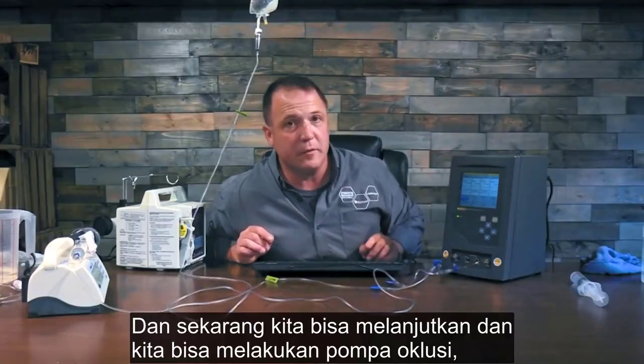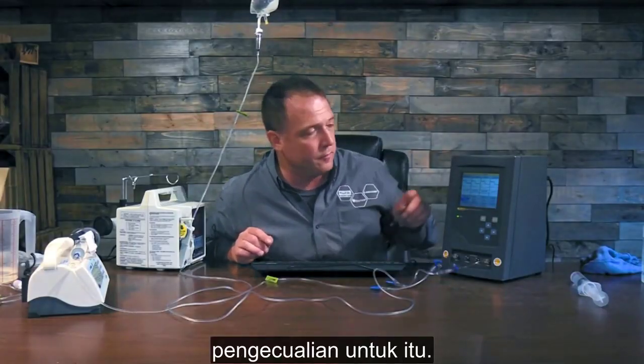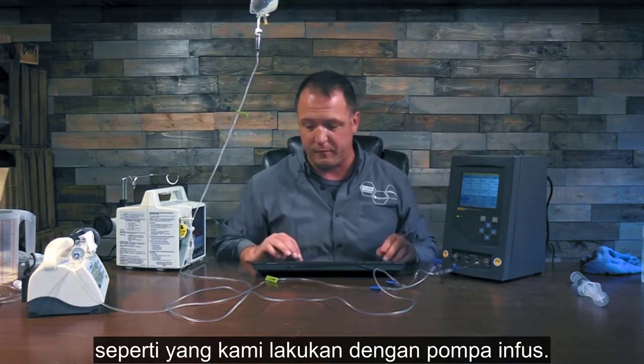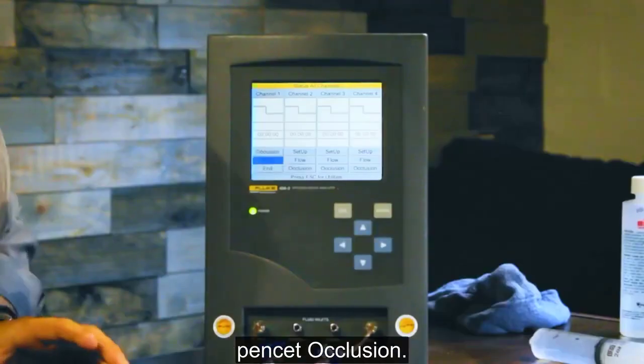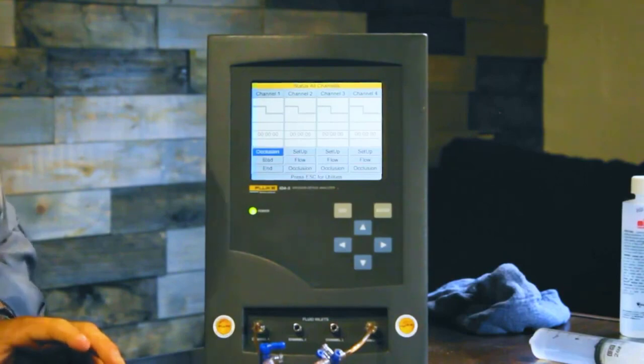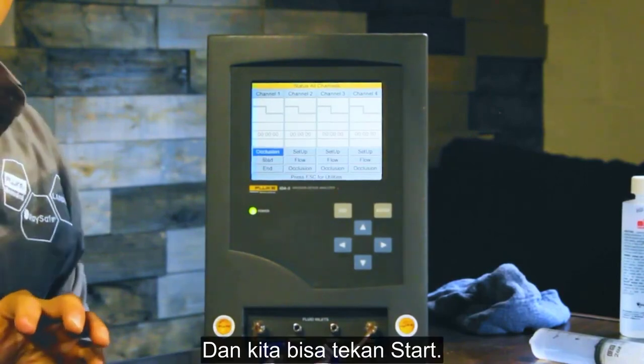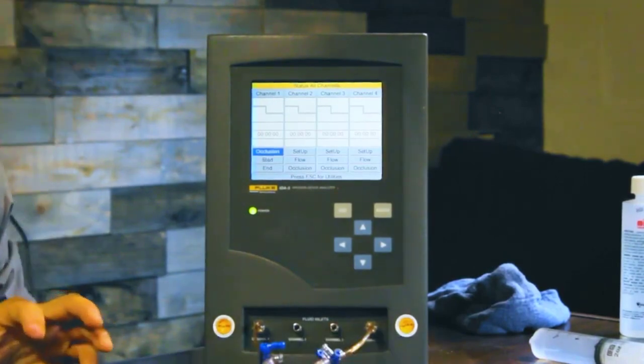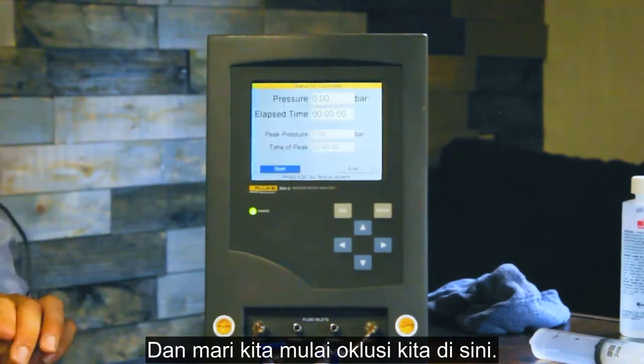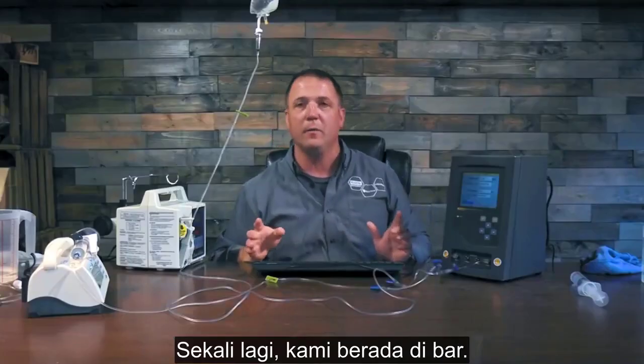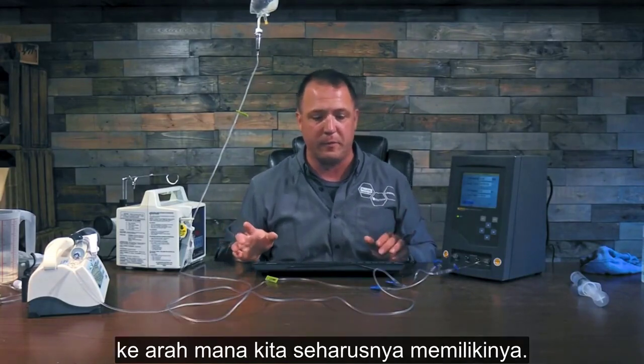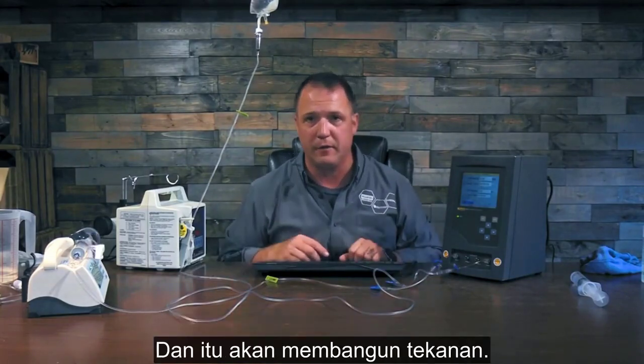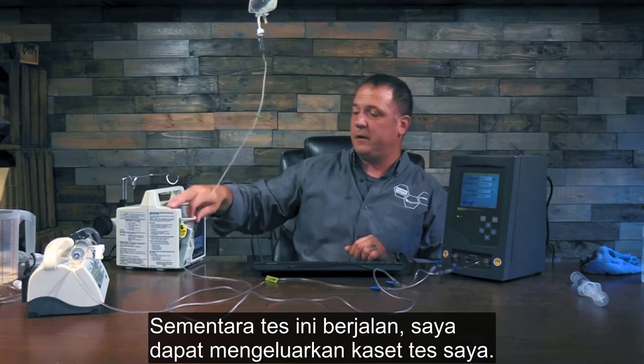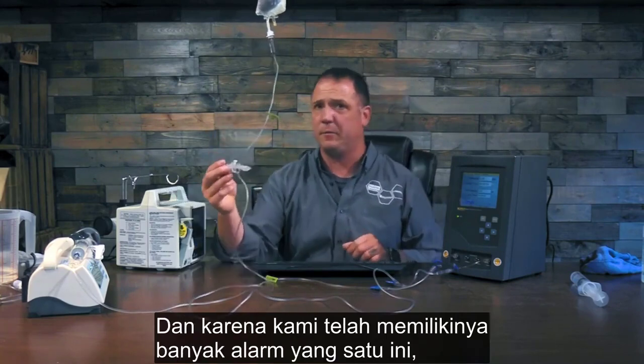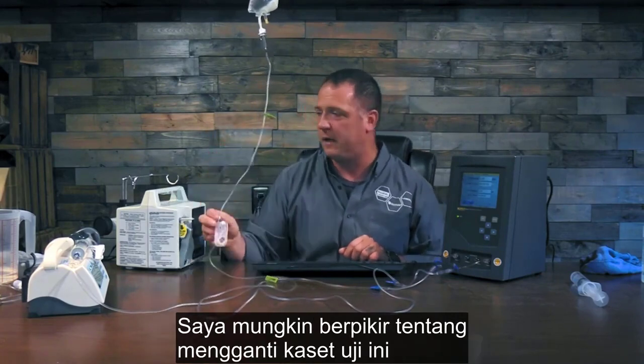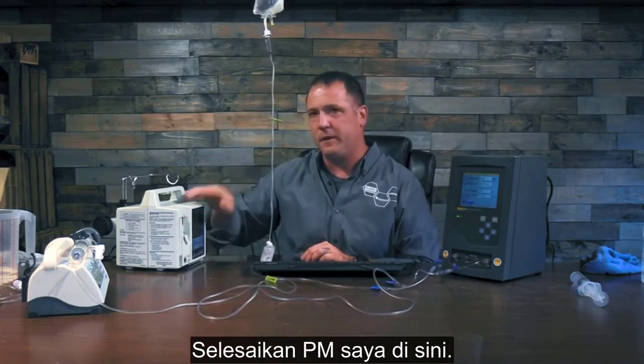And now we can go ahead and do the occlusion for that. It's going to be the same thing like we did with the other infusion pump. Go down to occlusion, and we can hit start here again and start our occlusion. Again, we're in bar. We'd have to find our manual to figure out for sure which way we're supposed to have it. And it's going to be building up pressure. While this test is going, I can take out my test cassette. And since we've had so many alarms on this one, I might think about replacing this test cassette if I had another one.